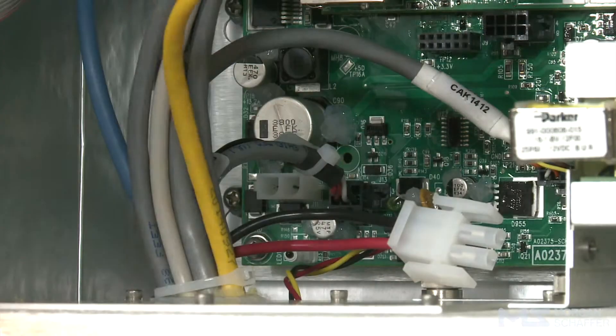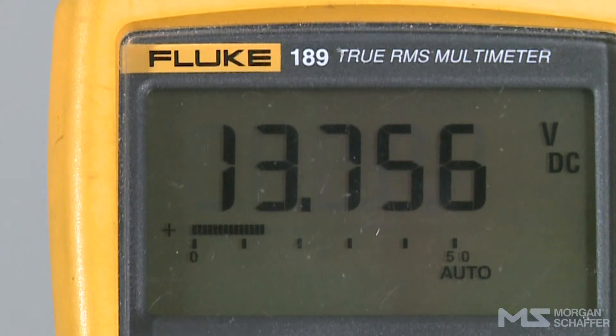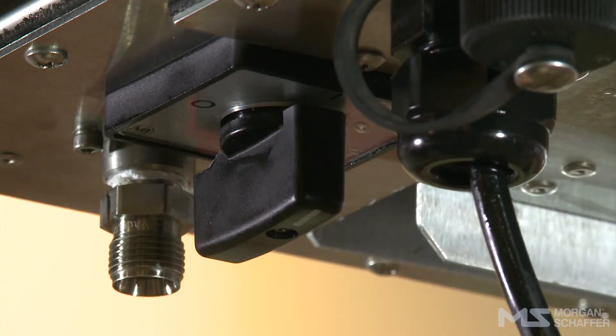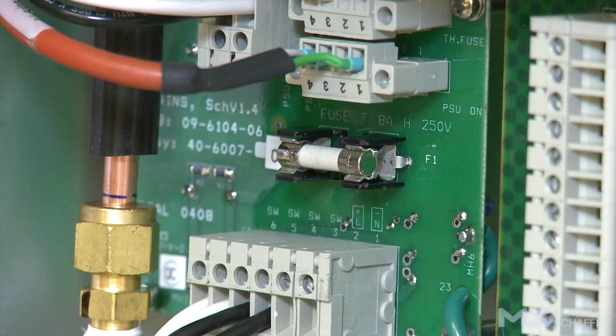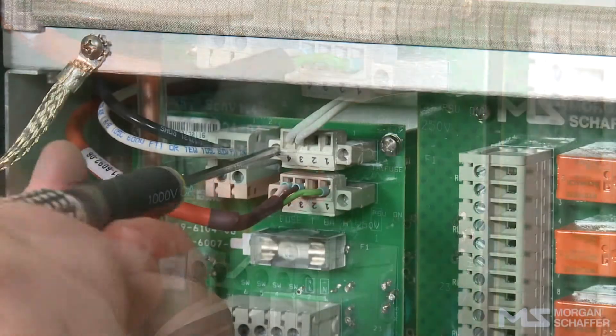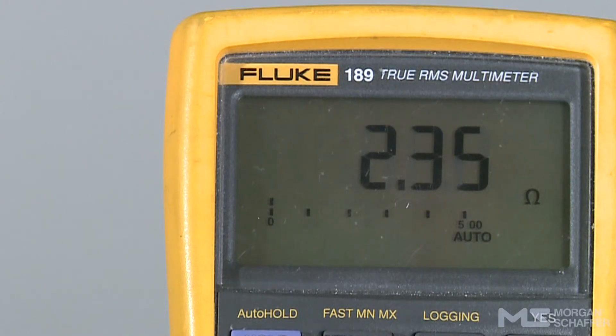Check the power supply of the power pack. Connect a multimeter between pins 1 and 2 of the TB2 connector. The voltage must be between 100–240 volts AC or 100–220 volts DC. If this is not the case, check the condition of the fuses. Check the power pack by connecting a multimeter between pins 1 and 2 of the J11 connector. The voltage must be stable and between 13.25 and 13.75 volts DC. If this is not the case, the power pack is defective — please contact Morgan Schaffer. Check that the fuses are functional. Turn off the Callisto and close its circuit breaker. Check the continuity of fuse F1 using a multimeter. Connect a multimeter between pins 3 and 4 of the J2 connector. There must be continuity between the pins. If the fuses are defective, they must be replaced.